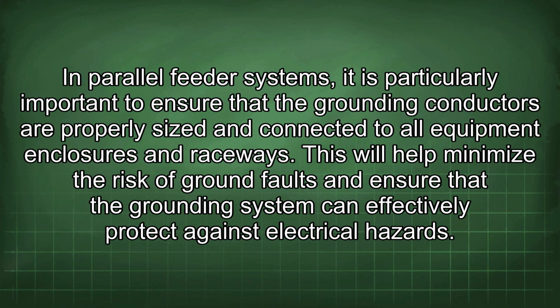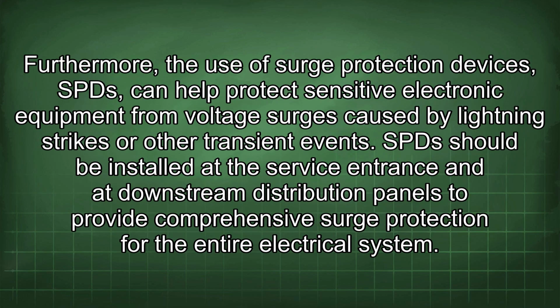In parallel feeder systems, it is particularly important to ensure that the grounding conductors are properly sized and connected to all equipment enclosures and raceways. This will help minimize the risk of ground faults and ensure that the grounding system can effectively protect against electrical hazards. Furthermore, the use of surge protection devices, SPDs, can help protect sensitive electronic equipment from voltage surges caused by lightning strikes or other transient events.